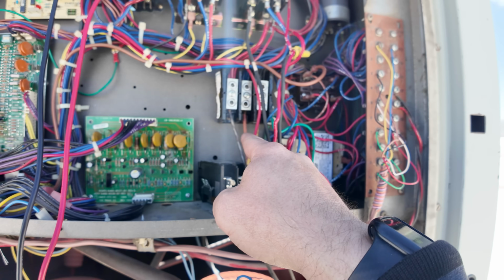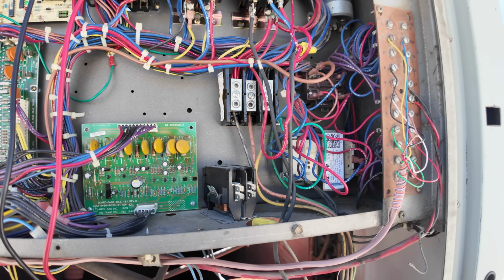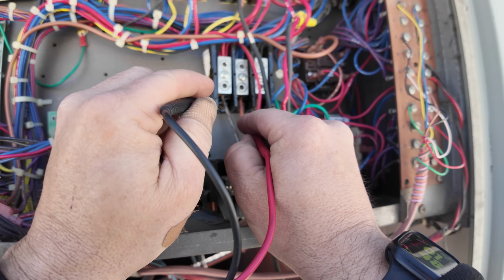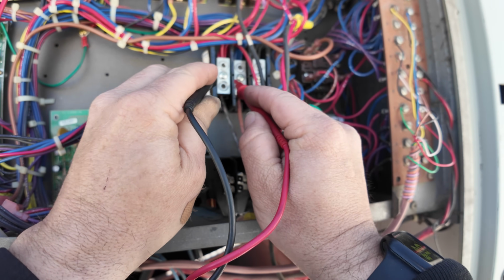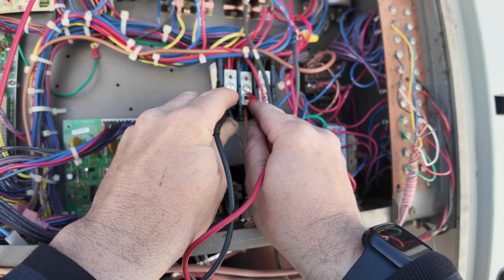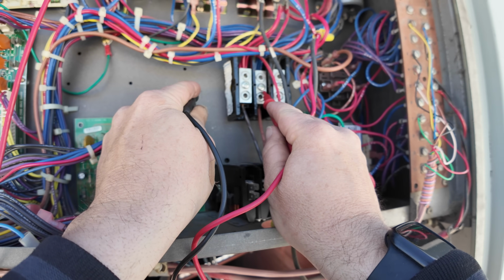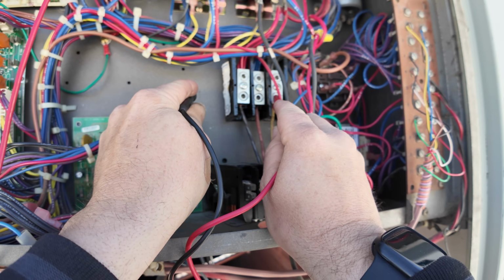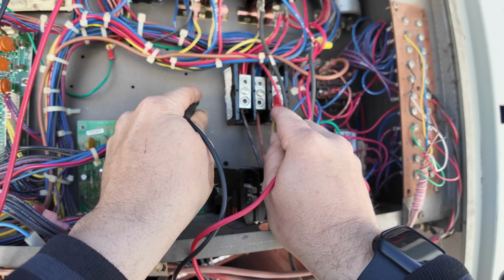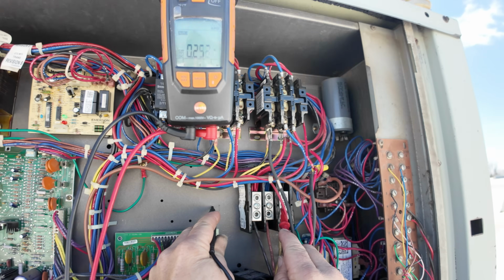I could have known that this was 480, 460 just by looking at the wire colors. Orange, brown, and yellow is traditionally that voltage. Blue and red is usually 208. So I always like to check between legs and to ground. Okay, everything's dead now.